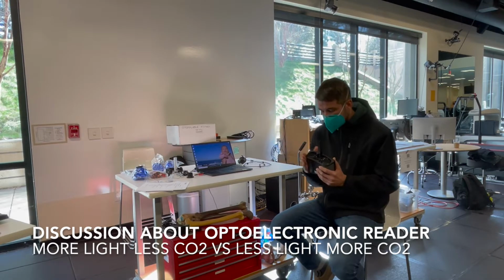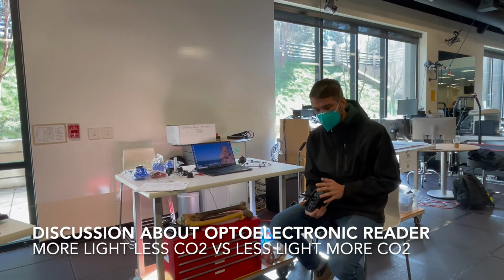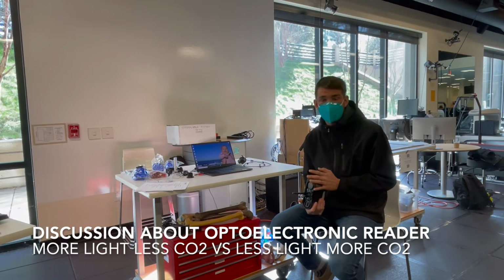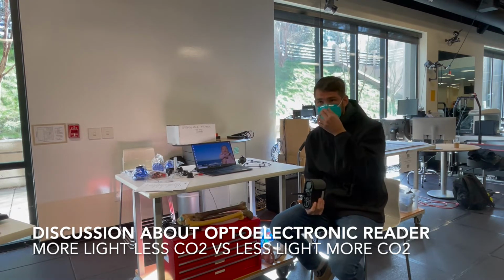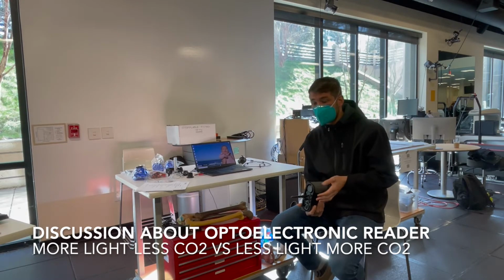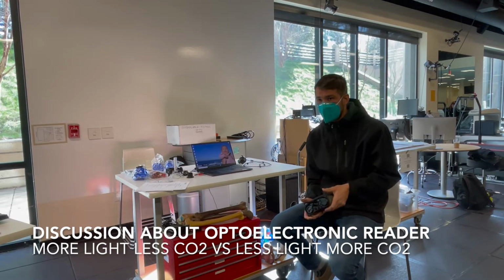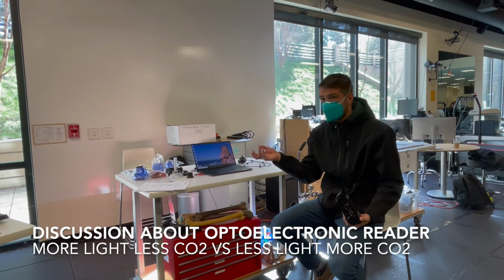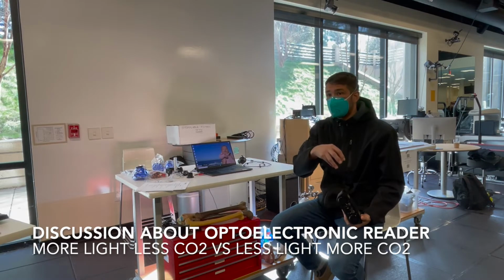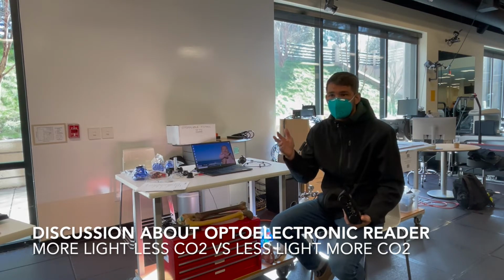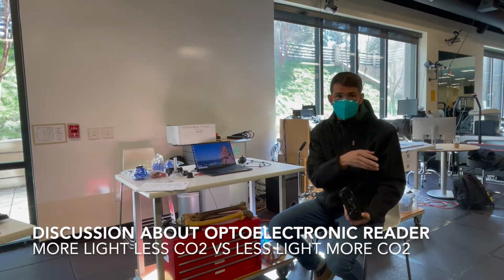Okay, so to just cover the analyzers real quick, the CO2 analyzer is a digital infrared analyzer, so it's going to be pretty much the same thing that you got in the CPET over there. And so that's why the calibration is so important, because of the way that the sensor takes its measurement. So basically an infrared light bulb sends light onto a photoreceiver, and the more CO2 in the line, the more light is absorbed, so the less light is actually being received on the photoreceiver.